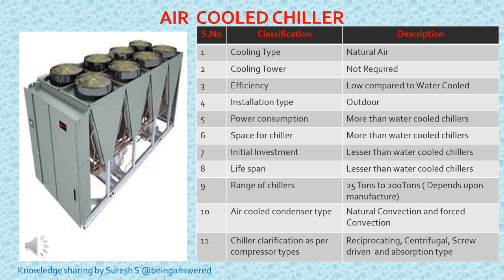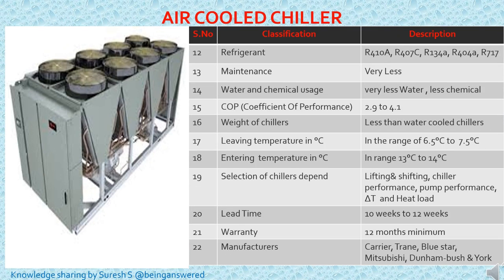Similarly, chiller classification as per compressor type: reciprocating, centrifugal, screw driven and absorption type. The refrigerant used in the system is similar to the water cooled chiller. In this, maintenance will be very less, so water and chemical usage will be very less. The COP, if you see, will be 2.9 to 4.1, whereas in the water cooled chiller it will be more. The weight of the chiller will be less compared to the water cooled chiller.